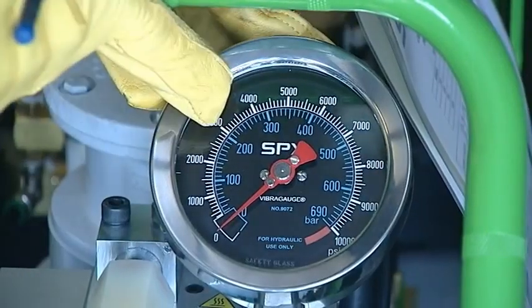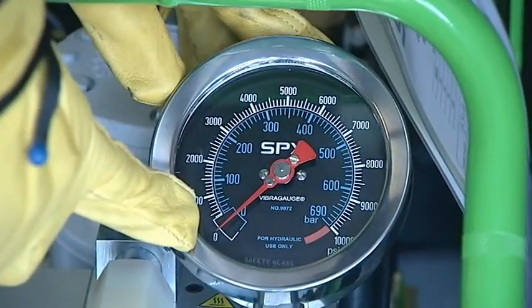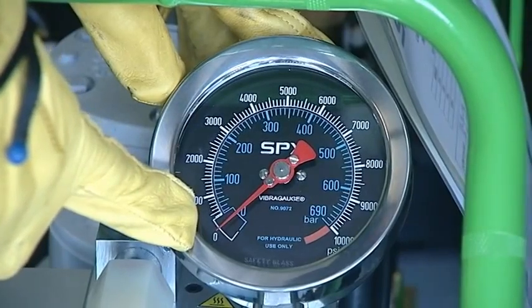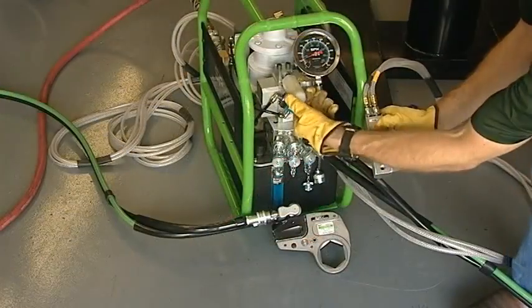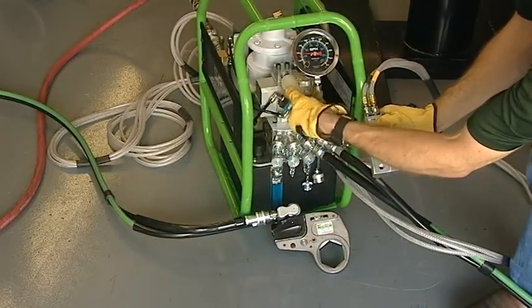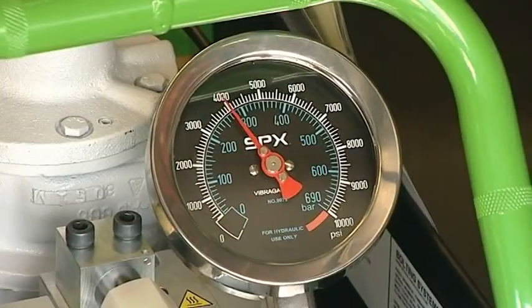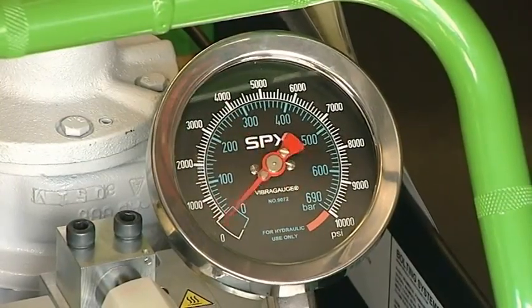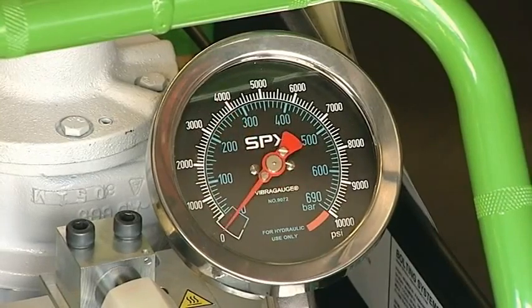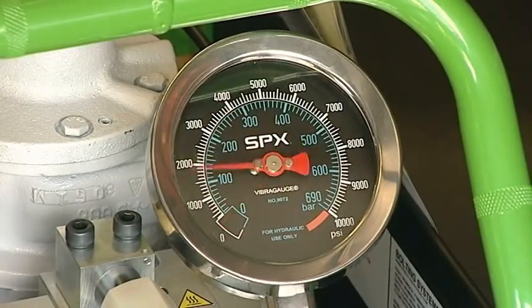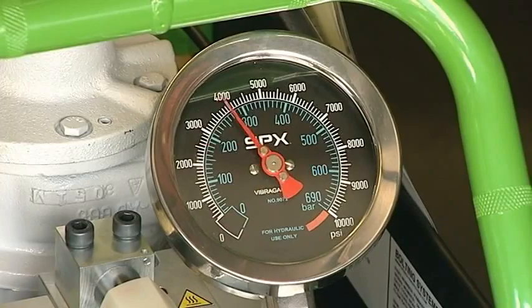The pump gauge reads in PSI, therefore you must convert foot-pounds to PSI. To set the pump to the correct PSI, hold down the advance button, turn down the torque control valve to the proper PSI, then release the advance button. Push the advance button once again to check the repeatability of the pressure setting.